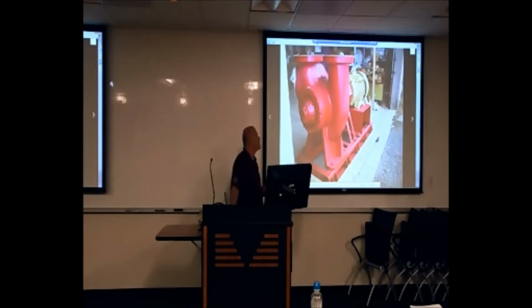One is for flushing of the bearing or the seal chamber if you wanted to. In this case, it's not hot water or anything that would require that, so internal flushing is fine. The other is where you can put an air vent. And what happens is, essentially, sometimes you see a pocket of air get on the top half of the pump and then water on the lower half of the pump. When it starts up, you'll know. It makes a big loud bang.